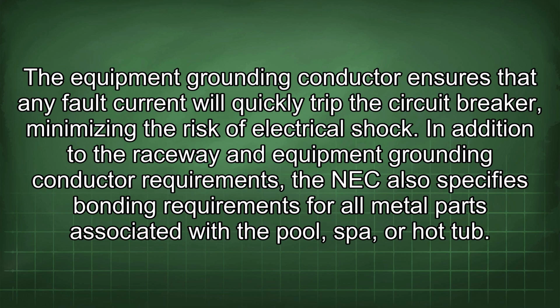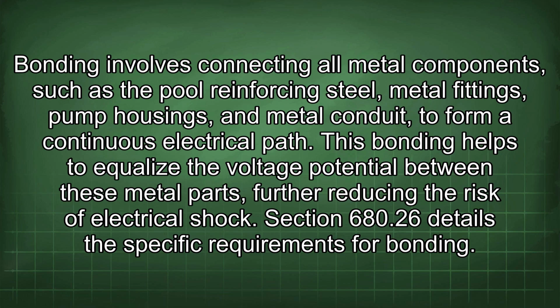The equipment grounding conductor ensures that any fault current will quickly trip the circuit breaker, minimizing the risk of electrical shock. In addition to the raceway and equipment grounding conductor requirements, the NEC also specifies bonding requirements for all metal parts associated with the pool, spa, or hot tub. Bonding involves connecting all metal components, such as the pool reinforcing steel, metal fittings, pump housings, and metal conduit to form a continuous electrical path. This bonding helps to equalize the voltage potential between these metal parts, further reducing the risk of electrical shock. Section 680.26 details the specific requirements for bonding.